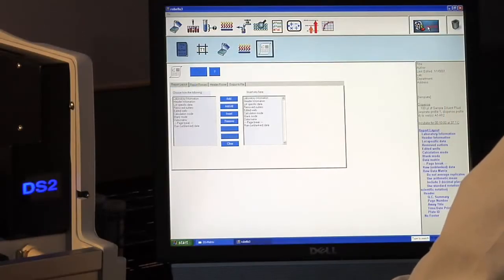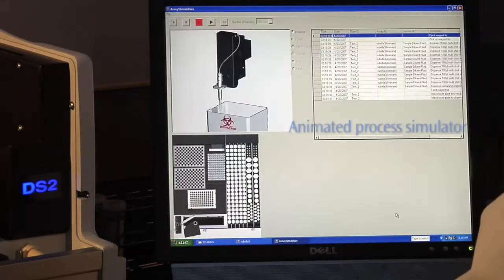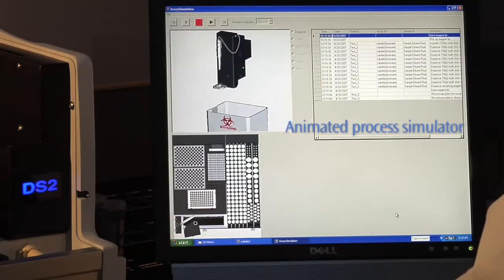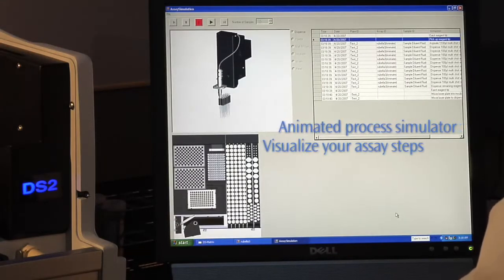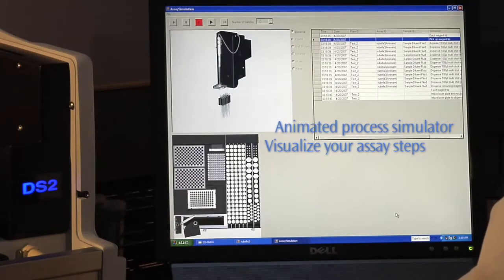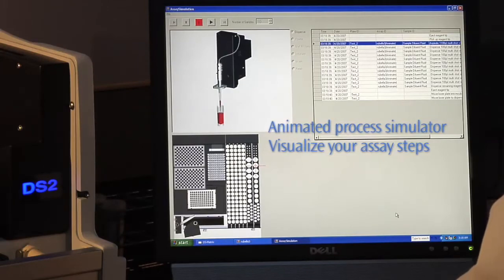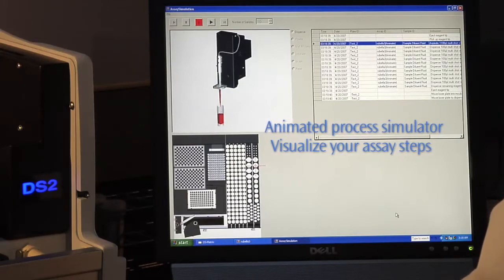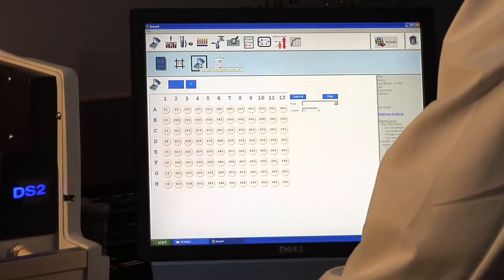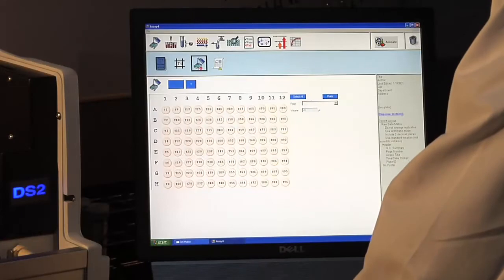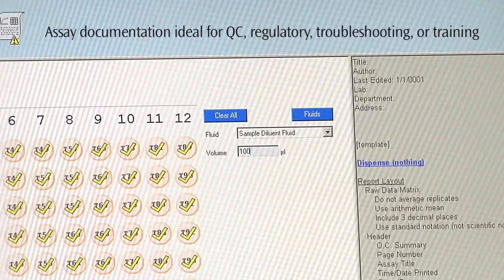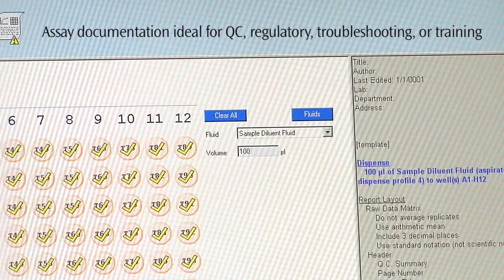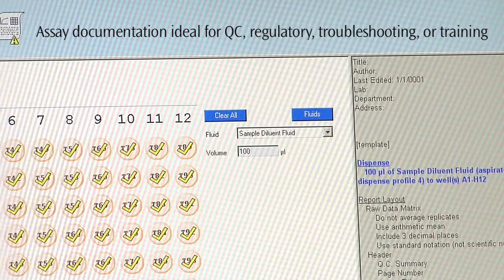No need to waste time with multiple test runs to validate your assay. The animated process simulator allows you to visualize the steps you've outlined, an invaluable tool for both trainees and experienced operators. The assay writer also creates a text description of your assay, which you can print out as documentation for QC, regulatory, troubleshooting, or training purposes.